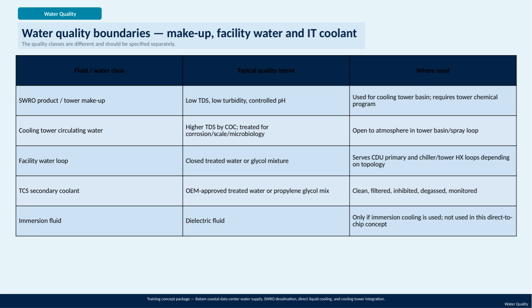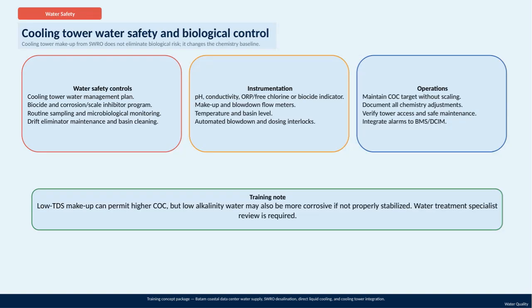Additionally, it's important to note the training concept package integrates knowledge of the Batam coastal data center's water supply, SWRO desalination, direct liquid cooling, and cooling tower integration, ensuring all aspects of water quality management are covered thoroughly. Let's talk about water safety in cooling towers, focusing on cooling tower water safety and biological control. Even when the makeup water comes from a seawater reverse osmosis or SWRO system, it doesn't eliminate biological risks. Instead, it changes the baseline chemistry of the water. This makes ongoing management critical.